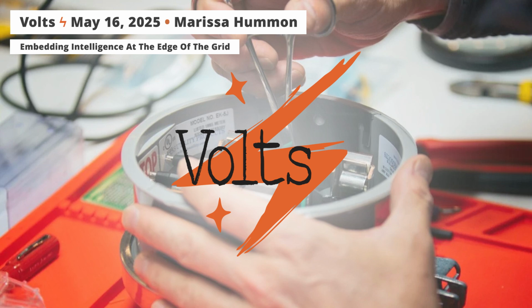Then the chip actually computes things like, does it see if an EV is starting to charge? And if so, was there a degradation in power quality the utility wants to be aware of? Or has it increased the loading on the transformer near that premise above 50%? The utility might want to start taking action, or at least managing for that new event. So it's really the piece that understands what those measurements mean.